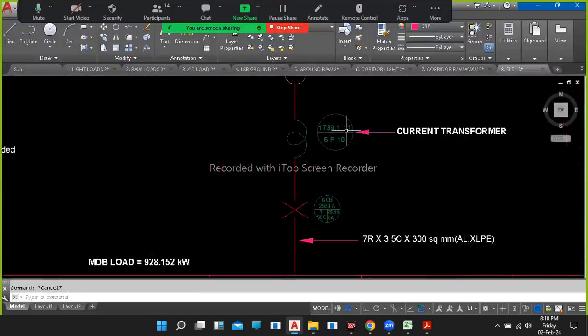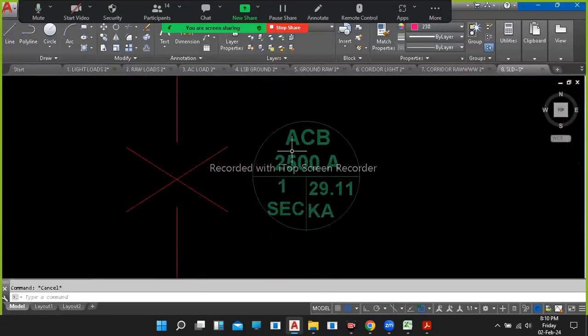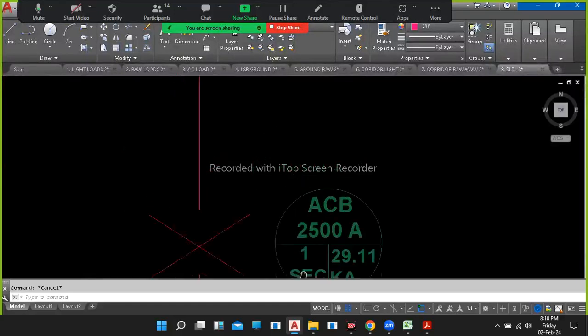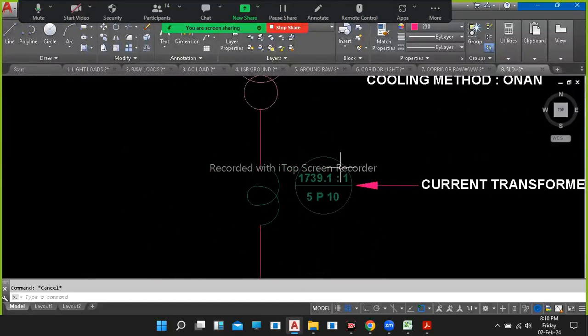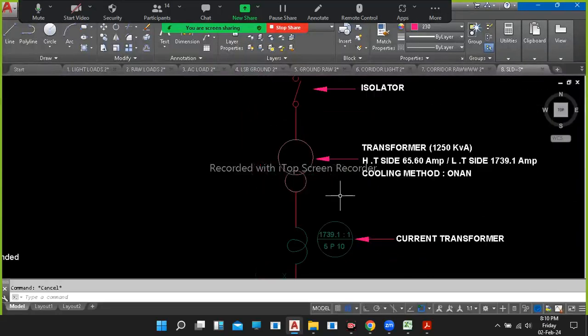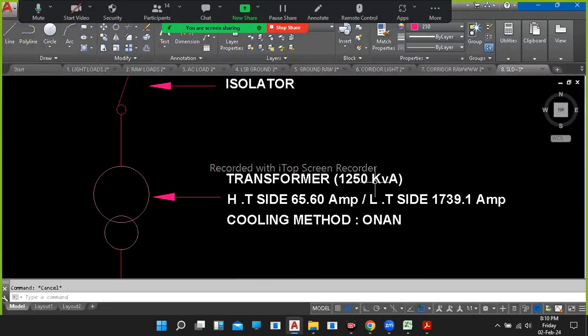Now based upon the MDB load, they calculated the circuit breaker size. He got ACB of 2500 amps with the fault current and tripping time, and the CT. This I'll tell you, the CT topics also. Ratio, protection class, and burden. I'll tell you. Then next transformer, he got 1250 kVA, where HT current, LT current, cooling method is oil natural, air natural.